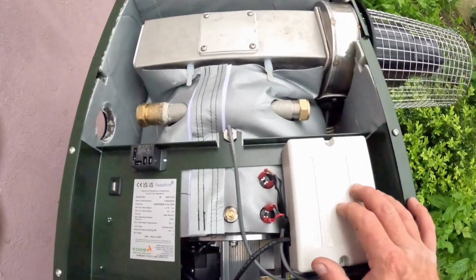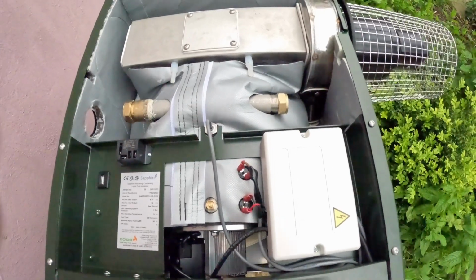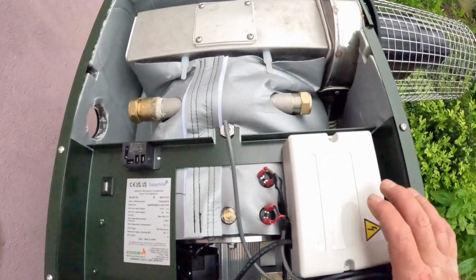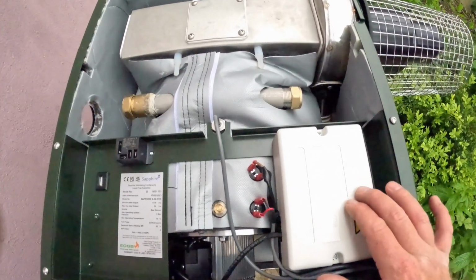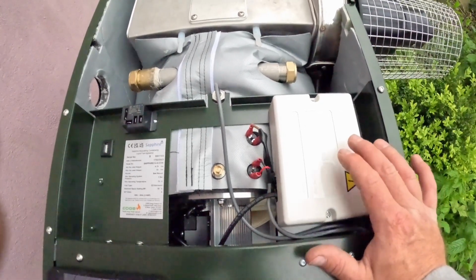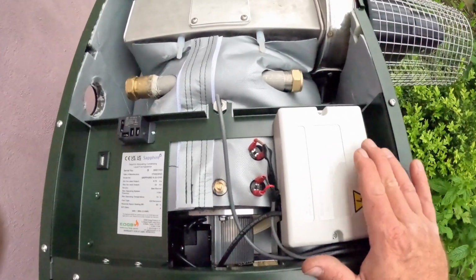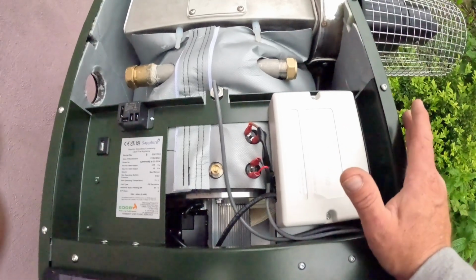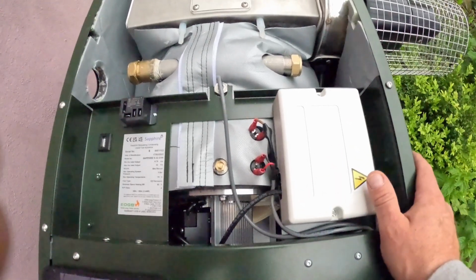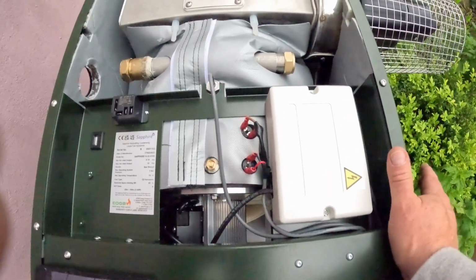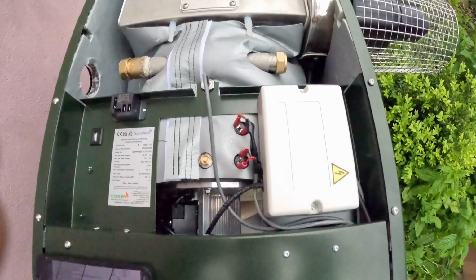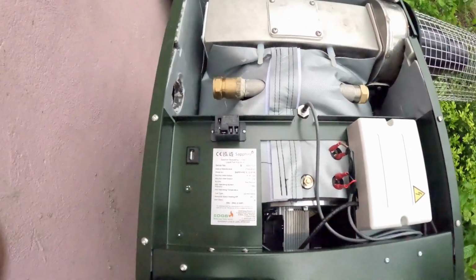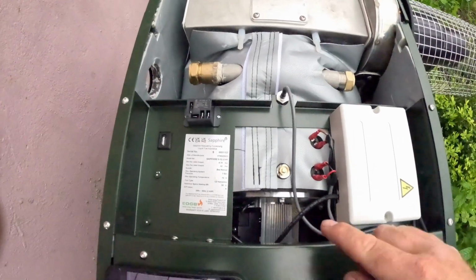This can actually run like a normal standard condensing boiler on a switch live. The only problem is I think you lose a lot of the modulation on that. So if you're going to go down that route and not fit OpenTherm, personally I wouldn't bother fitting one of these, because it's a bit of a waste of time, unless they obviously want to upgrade it soon after. But if you're going to fit one, you might as well fit OpenTherm straight off, or go and fit one of the other manufacturers, to be honest.